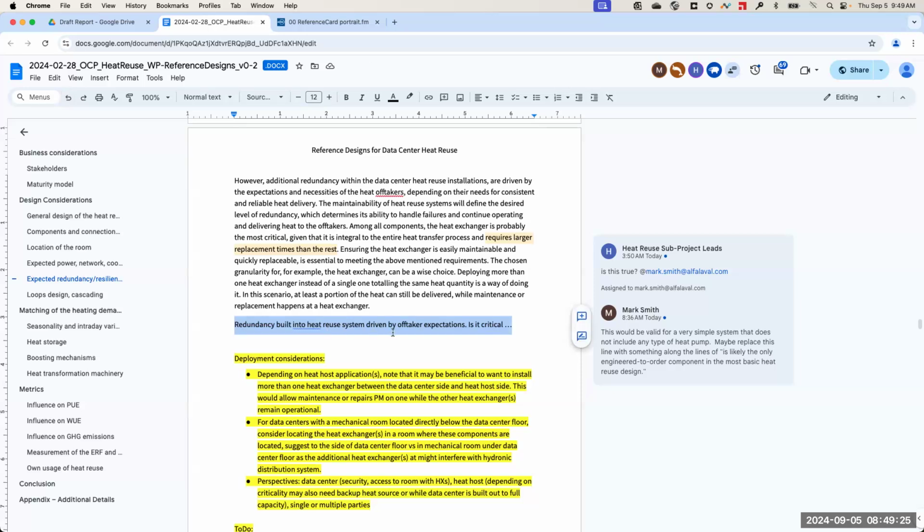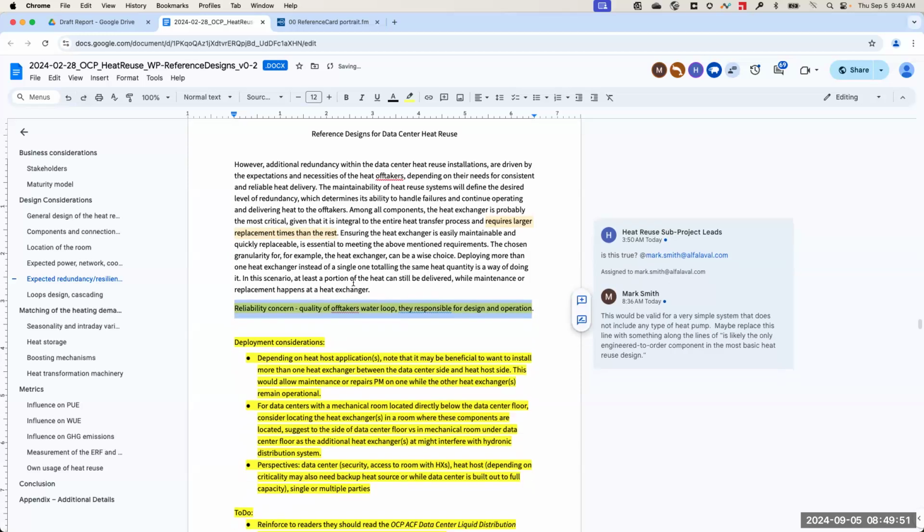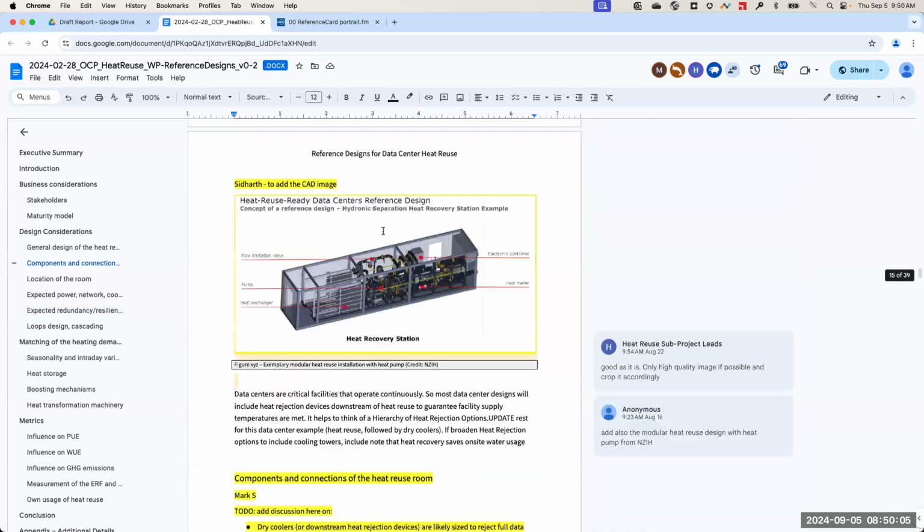Just a general mention of the implications and considerations they need to make on their water quality and the longevity of the shared equipment. To some people, water is just water, and we know that not all water is the same. I have this problem all the time with my chem engineering students. They think cooling water is the same as river water, is the same as well water, is the same as deionized water. Oh, it's just water. I say, no, you use river water and you exceed a 130 degree return temperature, you're going to have inverse precipitation. You're going to foul your heat exchanger in 5 weeks.